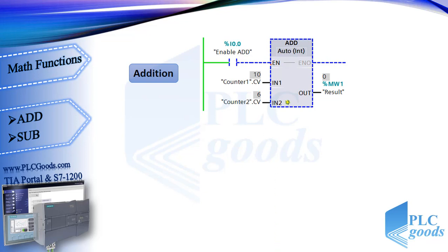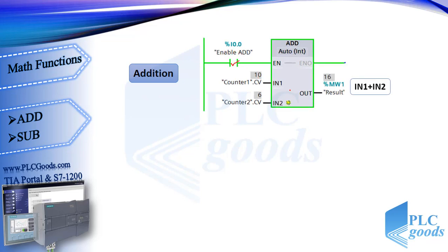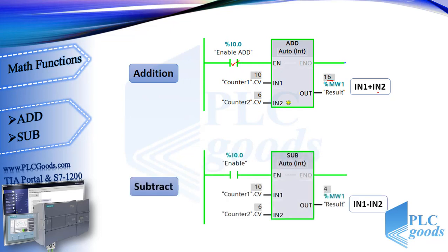This is the ladder symbol of the add function. For math functions we need to determine data types. This function adds the value at input IN1 and the value at input IN2, and outputs the sum. Here we have two values from two counters: 10 and 6, so the summation is 16. But here it shows 0 — why? This and other math functions have an enable input. If the I0.0 input is activated, the add function will do its work and store 16 at MW1 address.